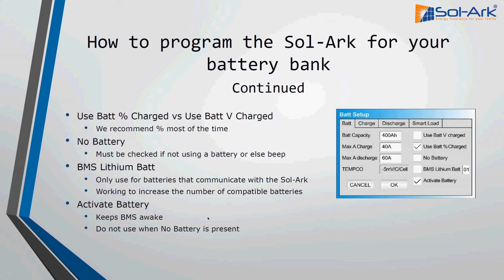Equalization is a bit interesting usually for folks. Yes, you don't technically need to equalize a lithium battery, but we still use the function called equalize for lithium batteries usually. We just set the voltage equal to the absorb and set the time to like an hour, just to make sure that the battery is all the way full every once in a while, every 30 days or so. Now, if you adamantly do not want to use this feature at all, just change the hours to 0, and it will never use the equalize function at all.